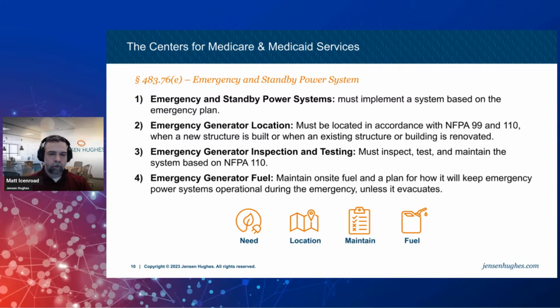First and foremost, as an emergency generator or standby power system is installed in your facility or currently maintained at your facility, it's really important that you are maintaining its inspection, testing, and maintenance per NFPA 110, and its location on 99. Those are specific to the type of generator and type of emergency power you have, but make sure you're doing that. If you're installing a new system, go read 110, or myself or folks at Direct Supply can help you understand what those testing requirements are, because that will be the maintenance going forward as the state and federal government will want you to maintain it.